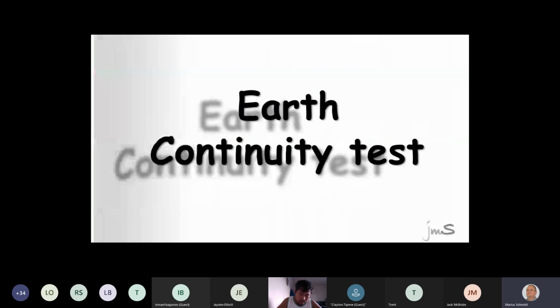Now, let's do an installation test. Before I'm going to do an earth test, I'm going to give you an appliance. If I say to you, look at the lead, what are you going to look at? Are you going to look if the plug is okay? Are you going to check if the phase, neutral, and earth pins are not bent closed? Are you going to check if your lead is not cracked? Are you going to confirm that the lead grip is correct? Are you going to confirm that the brown and light blue don't stick out? Hey, the green, brown, and blue, if that sticks out, and you get shocked somewhere, and you were the testing person, you're going to be in trouble, because no primary insulation is allowed to stick out. Now, who of you guys install downlights? You know that in a downlight there's like a little transformer.